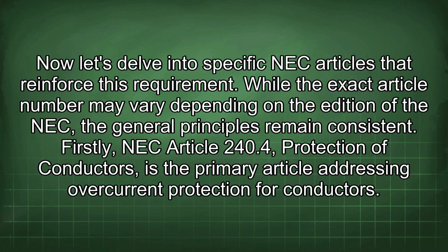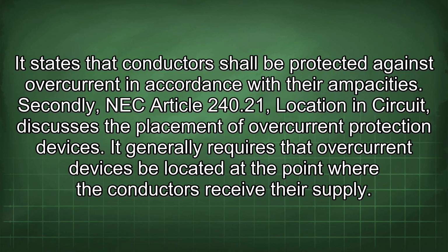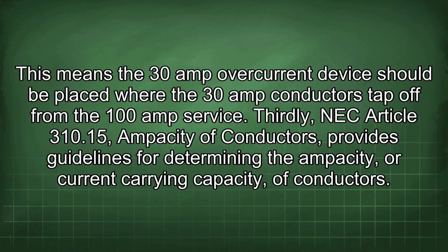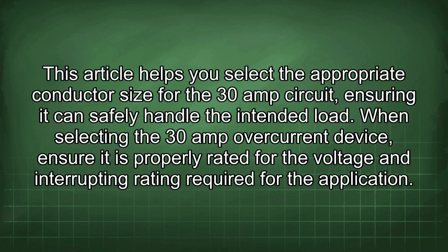Now let's delve into specific NEC articles that reinforce this requirement. While the exact article number may vary depending on the edition of the NEC, the general principles remain consistent. Firstly, NEC 240.4, Protection of Conductors, is the primary article addressing overcurrent protection for conductors. It states that conductors shall be protected against overcurrent in accordance with their ampacities. Secondly, NEC 240.21, Location in Circuit, discusses the placement of overcurrent protection devices. It generally requires that overcurrent devices be located at the point where the conductors receive their supply. This means the 30 amp overcurrent device should be placed where the 30 amp conductors tap off from the 100 amp service. Thirdly, NEC 310.15, Ampacity of Conductors, provides guidelines for determining the ampacity, or current carrying capacity, of conductors. This article helps you select the appropriate conductor size for the 30 amp circuit, ensuring it can safely handle the intended load.